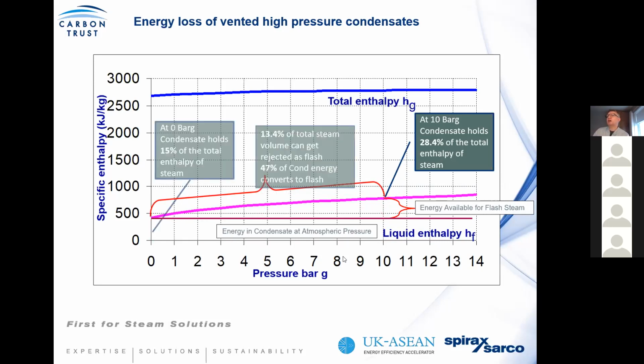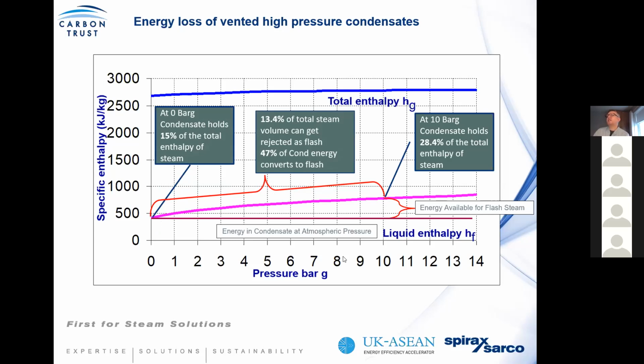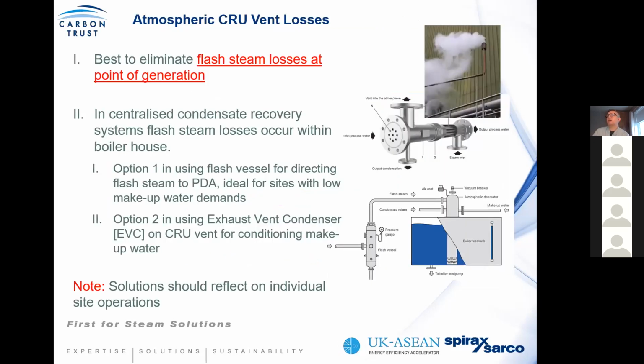However, when you look at what's lost, you could see that about 47% of the energy in that condensate gets rejected to atmosphere through evaporation, purely because through depressurization, you cause high pressure condensate to release its residual energy. In doing so, you will also cause about 13% of the volume of water to be lost as flash steam. So when you start looking at condensate recovery systems, it is best to eliminate the flash steam at source of generation. If it's a centralized condensate recovery system, you should look to see, can you take this flash steam to the boiler house?